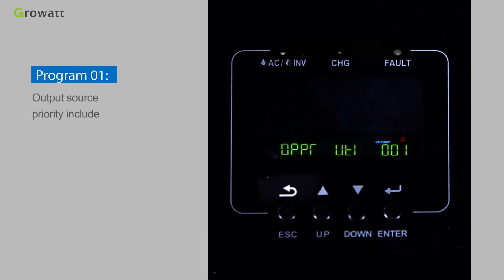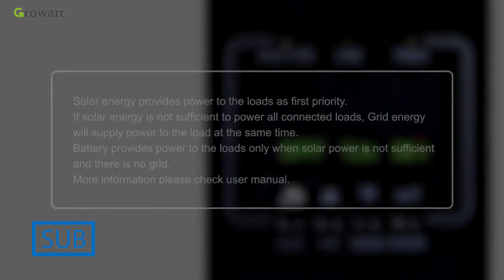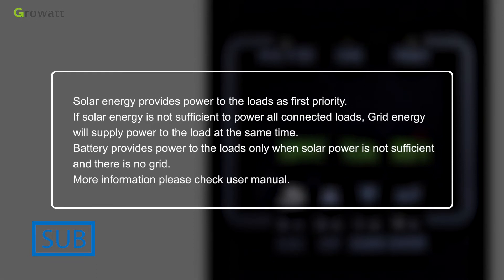Program 1 — Output source priority includes SOL, UTI, SBU, and SUB modes. In SOL mode, solar energy provides power to the loads as the first priority. If solar energy is not sufficient, battery energy will supply power simultaneously. Grid provides power only when solar energy is not available or battery voltage drops to the low-level warning voltage set in Program 12. In SUB mode, solar energy is still the first priority, but if insufficient, grid energy supplies power simultaneously. Battery provides power only when solar power is insufficient and grid is not available.